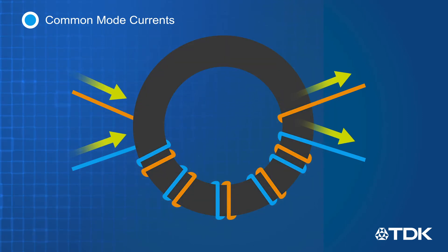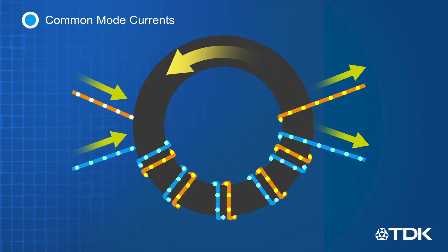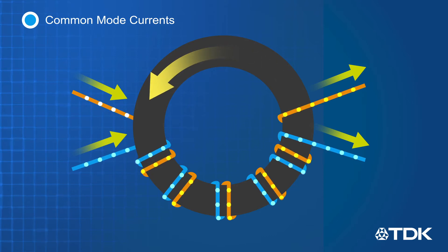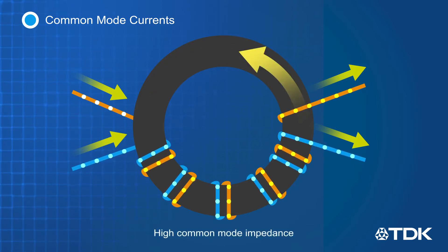Common mode currents flow into the wires in the same direction. The current flow through each wire creates a magnetic field, and because the current flow is the same direction for both wires, the magnetic field current adds together. This results in a high common mode impedance and filters out common mode noise.